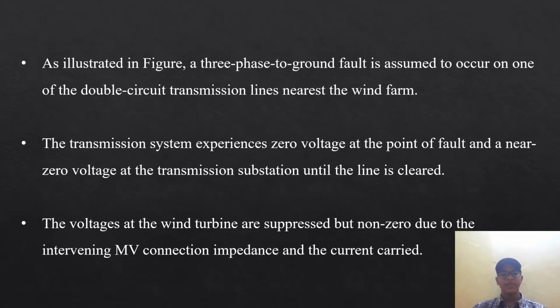As illustrated in the figure, a three-phase to ground fault is assumed to occur on one of the double circuit transmission lines nearest to the wind farm. The transmission system experiences zero voltage at the point of fault and near zero voltage at the transmission substation until the line is cleared. The voltages at the wind turbine are suppressed but non-zero due to the intervening MV connection impedance and the current carried.